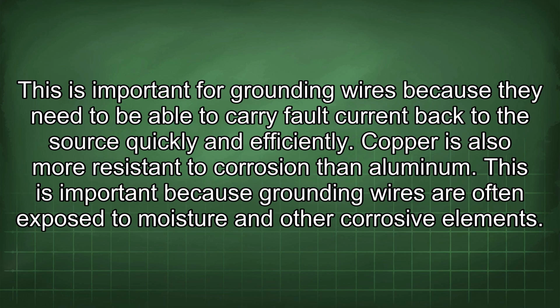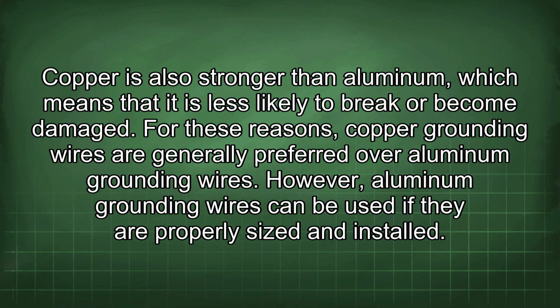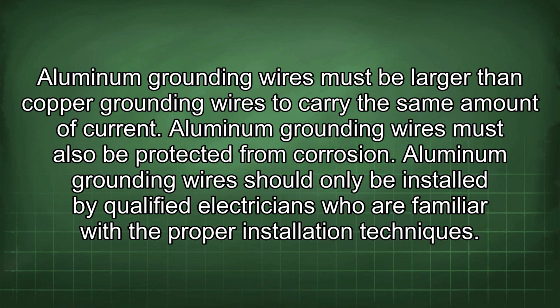This is important because grounding wires are often exposed to moisture and other corrosive elements. Copper is also stronger than aluminum, which means that it is less likely to break or become damaged. For these reasons, copper grounding wires are generally preferred over aluminum grounding wires. However, aluminum grounding wires can be used if they are properly sized and installed. Aluminum grounding wires must be larger than copper grounding wires to carry the same amount of current. Aluminum grounding wires must also be protected from corrosion. Aluminum grounding wires should only be installed by qualified electricians who are familiar with proper installation techniques.